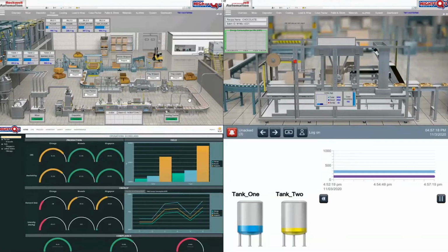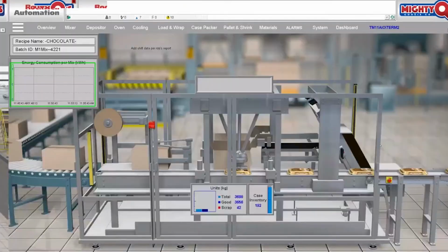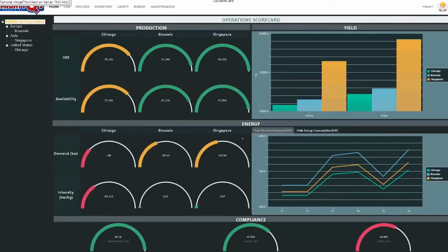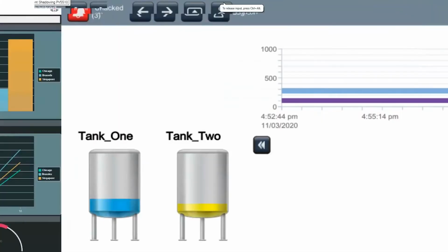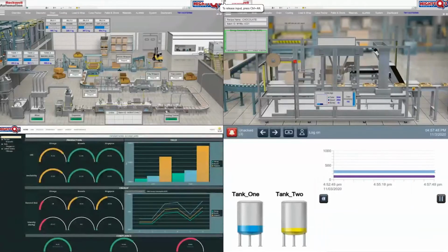So what's very powerful here is I now have 4 completely different pieces of content on one terminal. I don't have to have a separate KVM to have different keyboards and mice channeled through so the operator can use one. And I can bounce from one unit to the next. And I have things set up so that if I click on it with the left button, I go to full screen. And I have the ability to then move around and do what I want. I also put on side sliding. So what that basically means is I can go from content to content simply by going back and forth. And then if I right click anywhere, it goes right back to tiling because I set those things up in ThinManager to happen. So this is tiling, and this is very powerful.